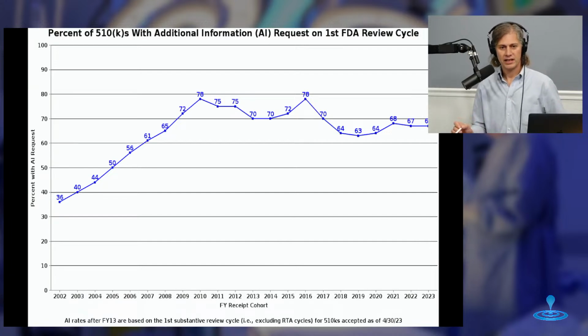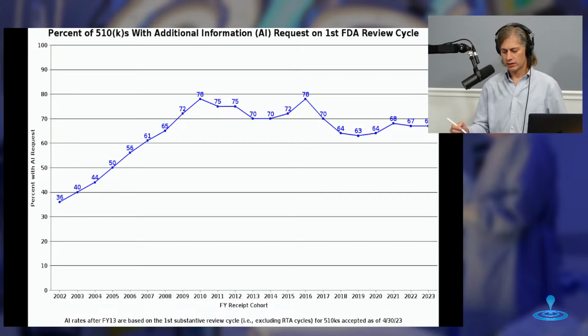What percent of 510Ks got that additional information request in that first FDA review cycle? Right now, that's around 67% for the last few years. That's pretty good. That means that they don't have a lot to ask on maybe 30% of the applications. But compare that to back in 2002, when the FDA only did additional information requests on about a third of the applications. That's quite a difference, going from 36% to 67%.